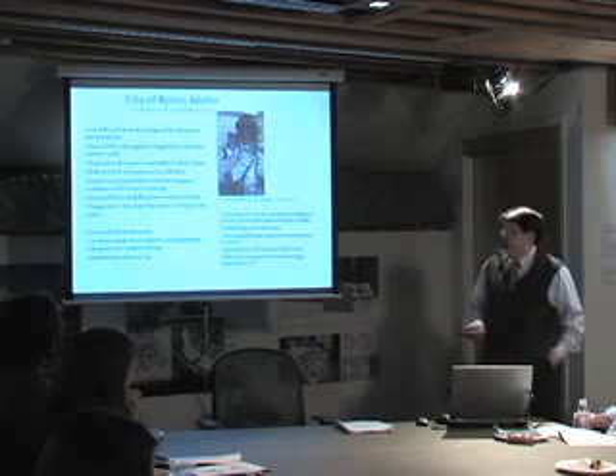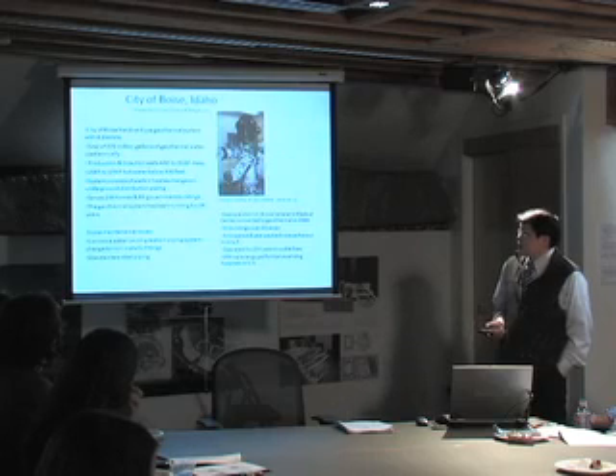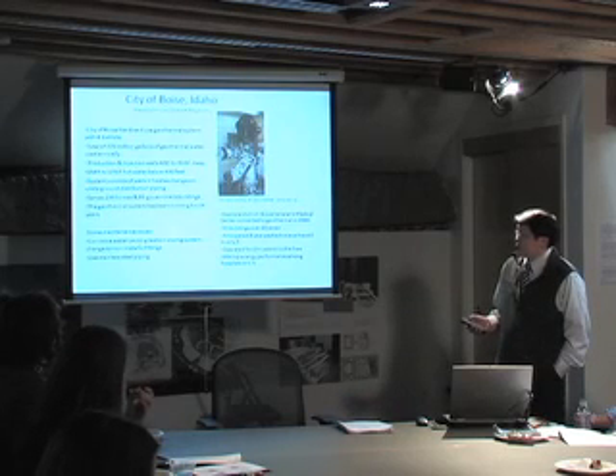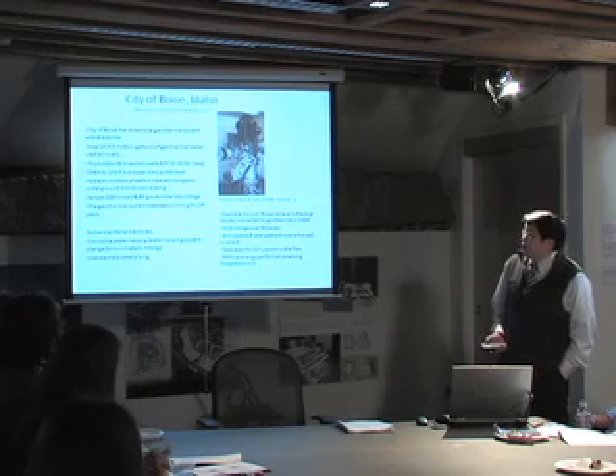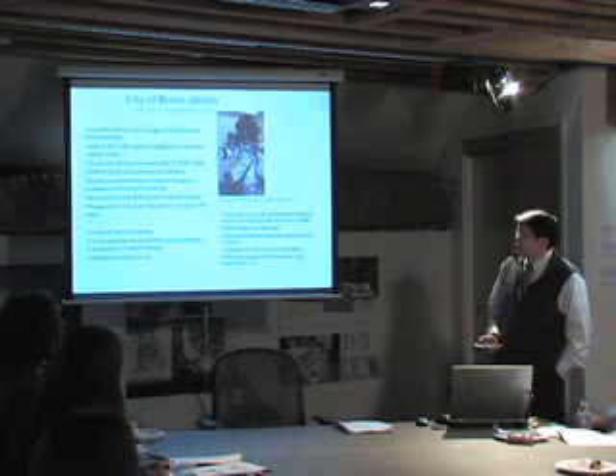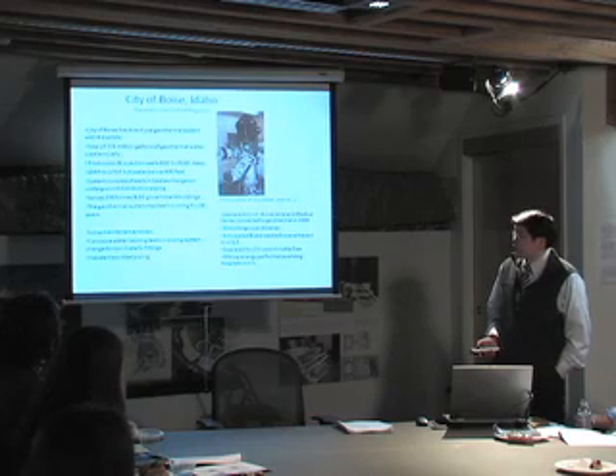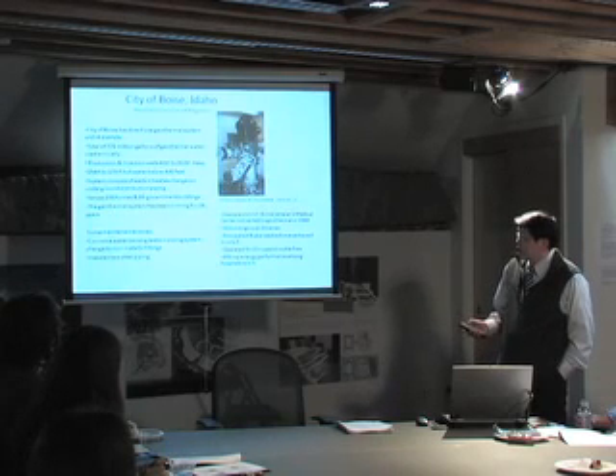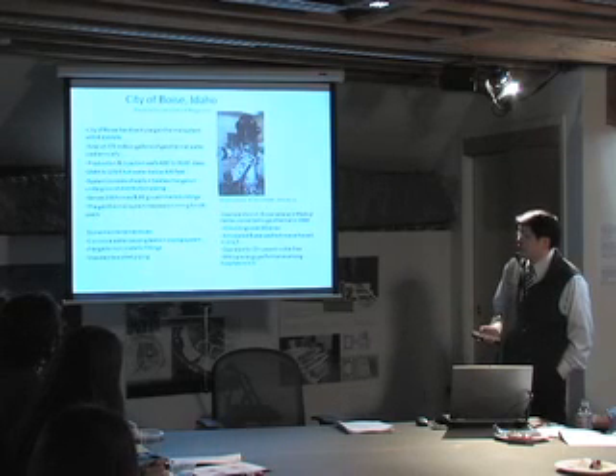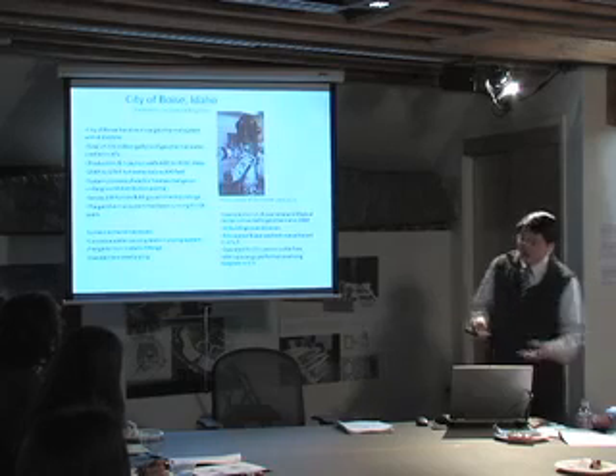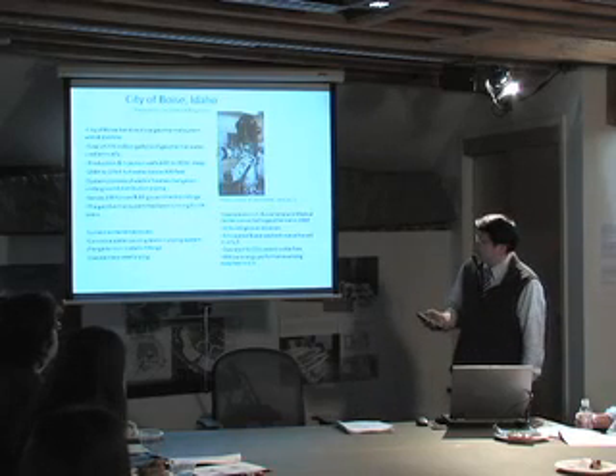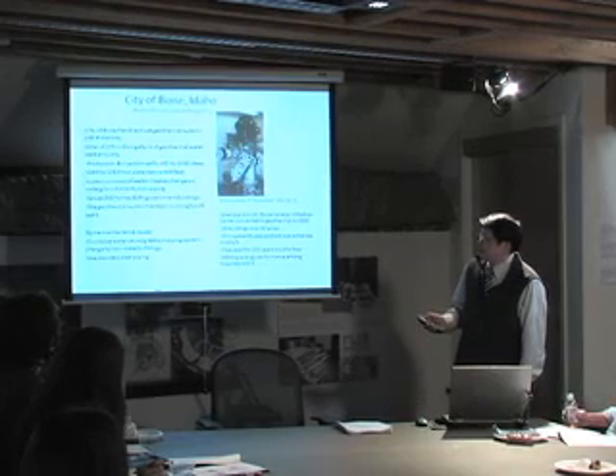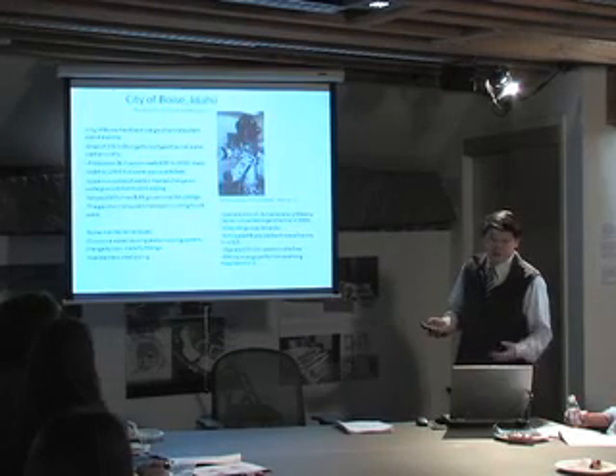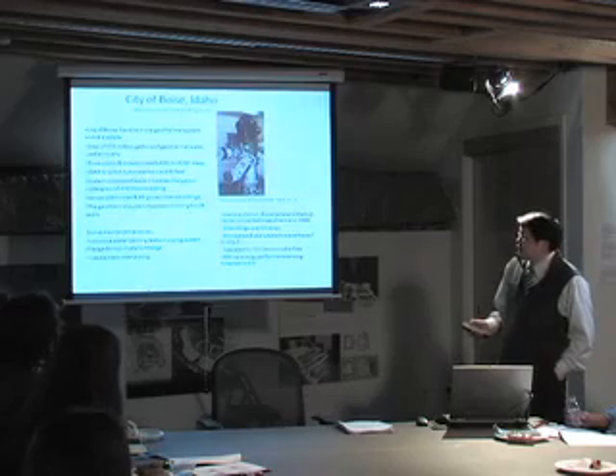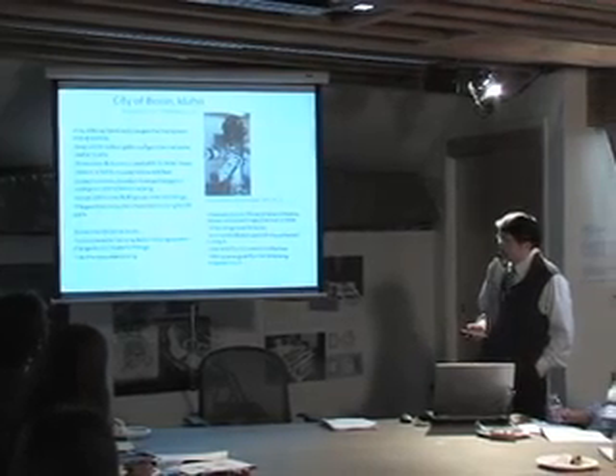So the city of Boise, Idaho, created a geothermal system with 4 districts. They pump a total of 775 million gallons of geothermal water from underground annually. And they drill the production and injection wells from 400 feet deep to 3,100 feet deep, because to get that high temperature water, you have to drill that deep. Sometimes they get the hot water from 400 feet deep, which is very desirable. Temperature range from 154 degrees to 175.